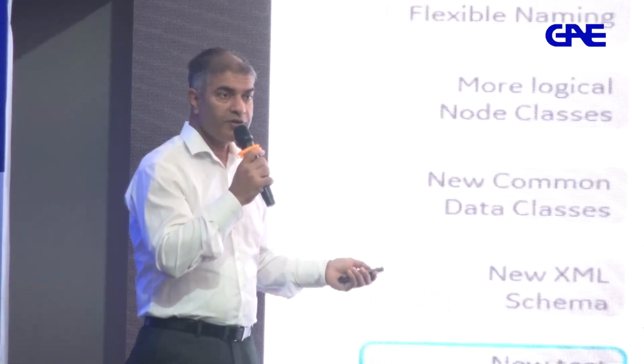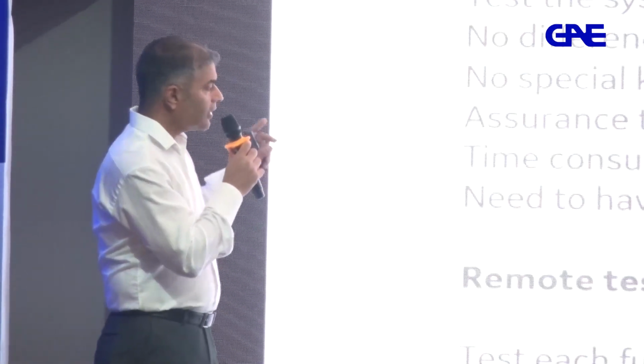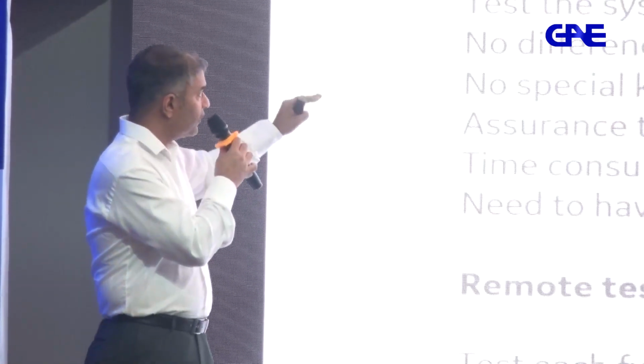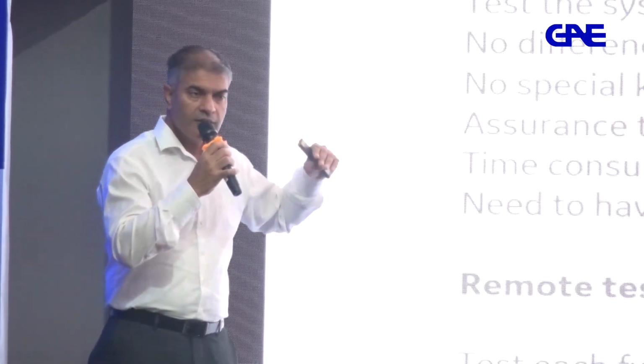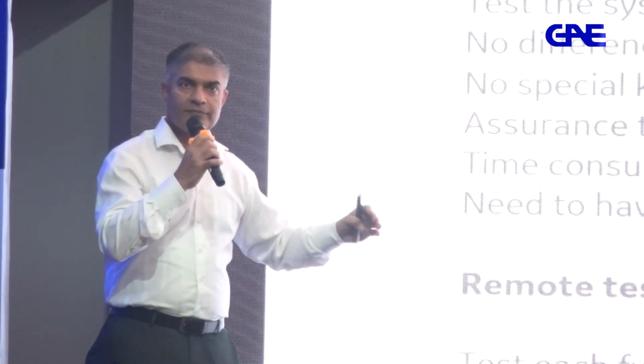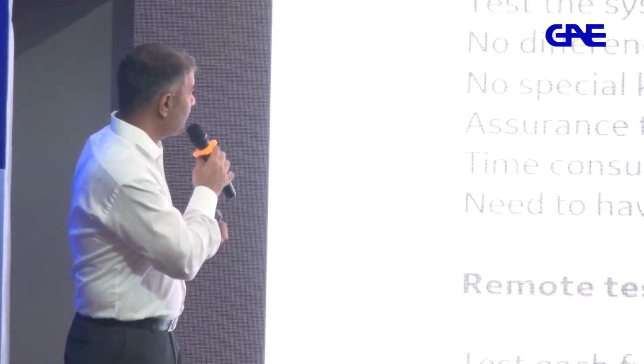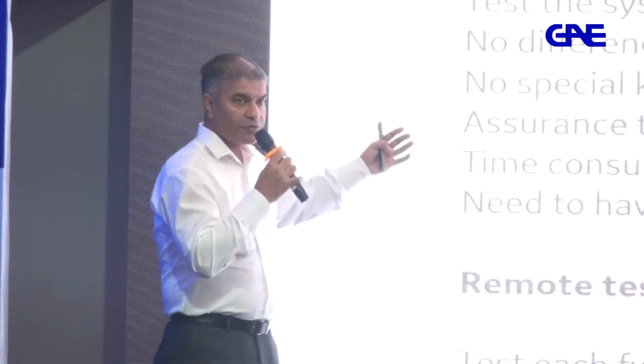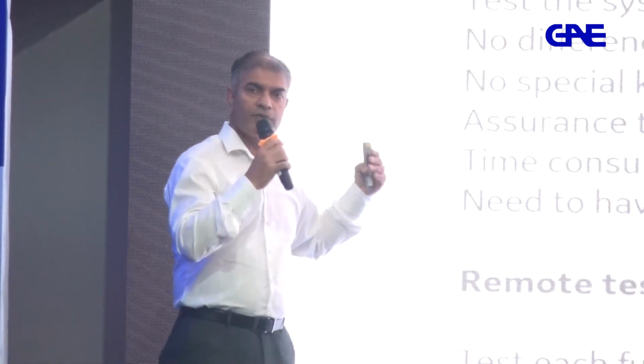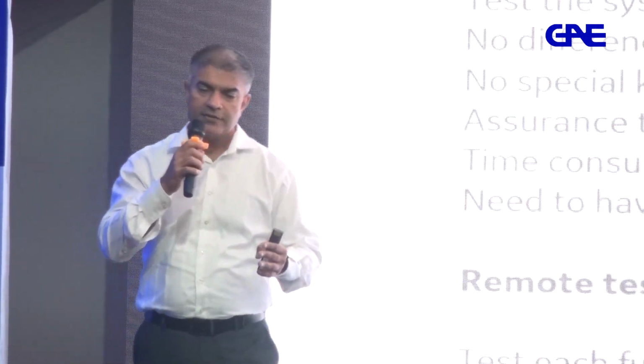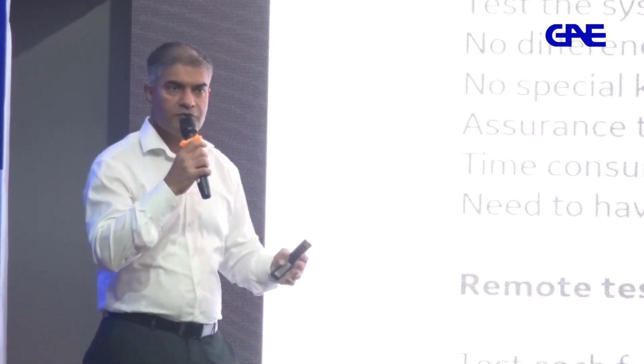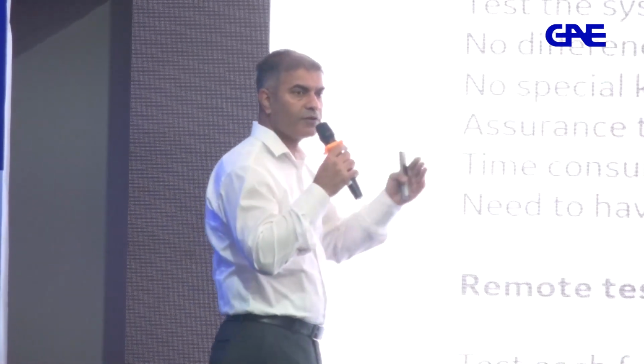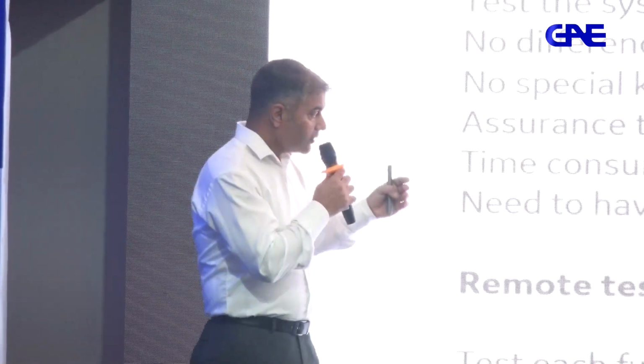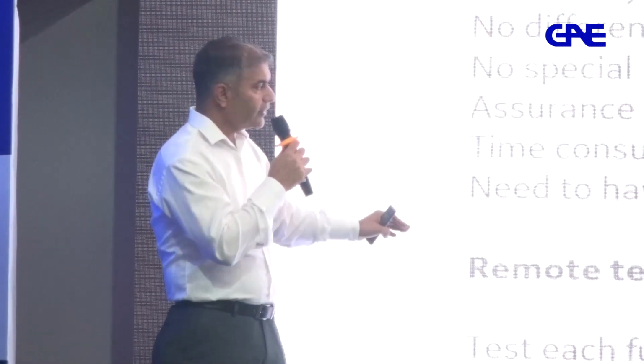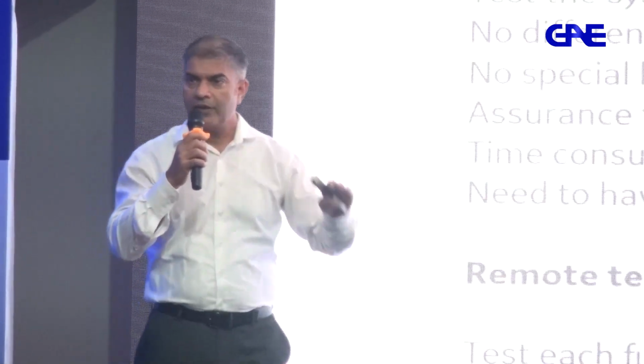Testing is very important, right? Okay, so there are basically two ways of testing. One is conventional, so test from the analog inputs. Five minutes, okay, I'll finish in 5 minutes. That's the conventional approach, as we do in a conventional substation. So we inject currents and voltages, and if you adopt the same approach, you have to inject currents and voltages in your switch yard, right? The alternate way of testing is remote testing in service without affecting anything.